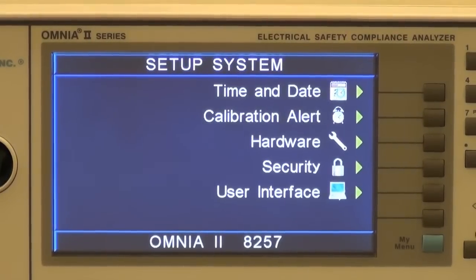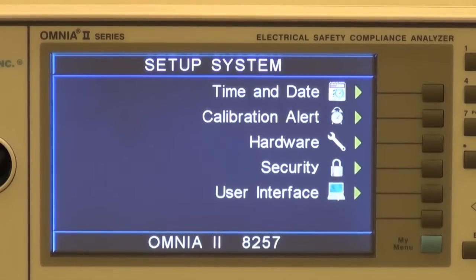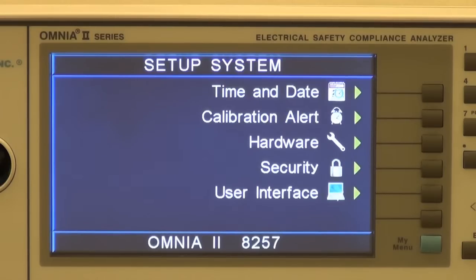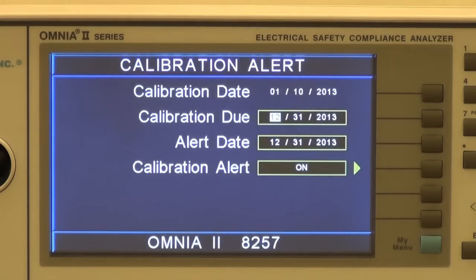Now that we've set the time and date on the unit, we'll want to set the calibration alert. The calibration alert is a feature that will allow the instrument to give an advanced alert that the calibration of the instrument is coming due. From the System Setup screen, press the Calibration Alert soft key. The Calibration Alert settings screen will now be displayed.